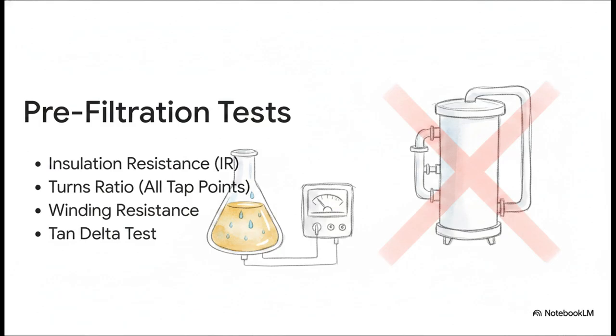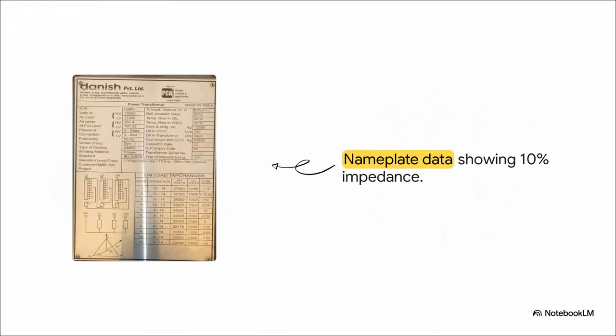Let's talk about percentage impedance, specifically when it's marked at, say, 10%. This single number, stamped right there on the equipment's nameplate, dictates the absolute maximum short-circuit current the system has to withstand. It's a simple but absolutely vital calculation. By dividing the rated current by this percentage impedance, engineers can predict the exact fault current during a short circuit. And that tells them exactly what rating their protection equipment needs to be to actually survive a worst-case scenario.